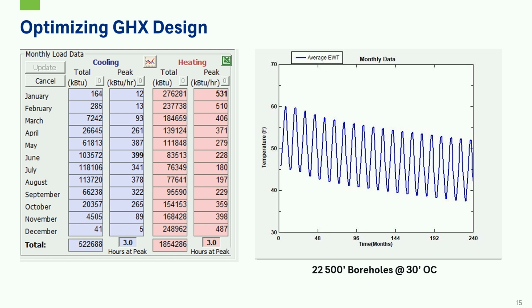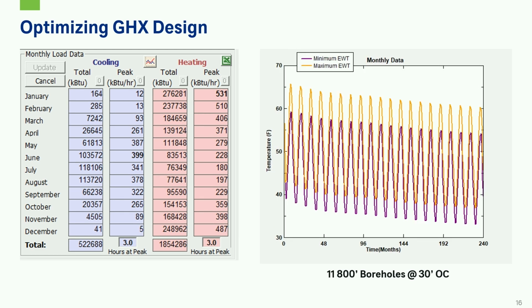Looking at those annual loads at the bottom there, we have about 500,000 kBTUs of cooling, and then about 1,850,000 kBTUs for heating over the year. So that's why we see that heating dominant thermal drift. So we ran with GLD, and these are the results we got with 22 500-foot boreholes spaced out 30 feet on center. And then we reran it, knowing that we had some space constraints on the site, and we reduced down to 11 boreholes, and then we increased that length to 800 feet, keeping that 30 foot on center.